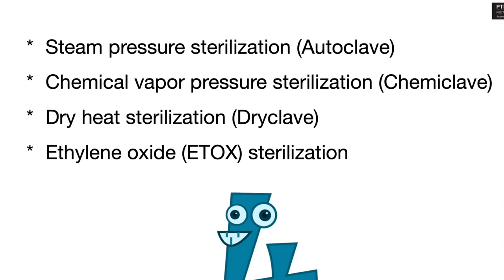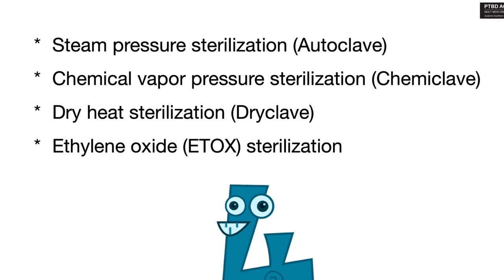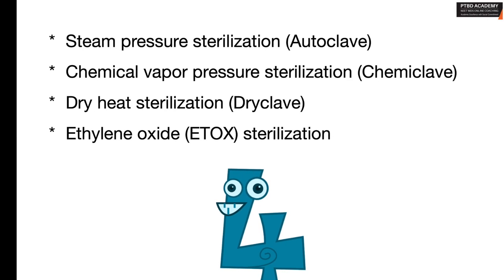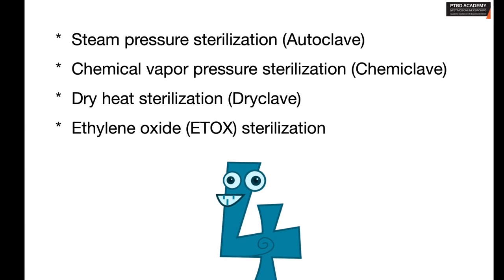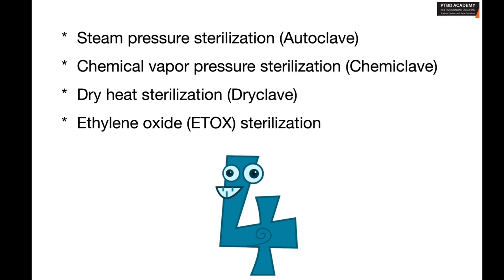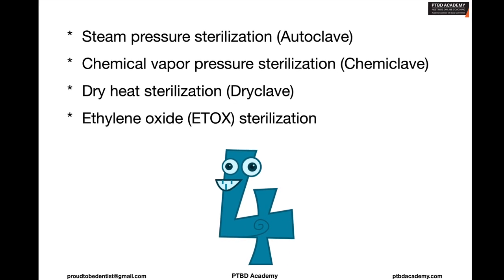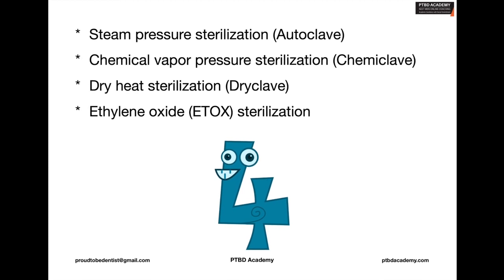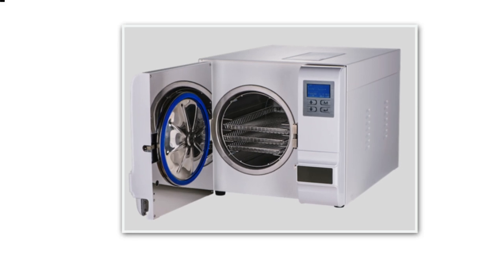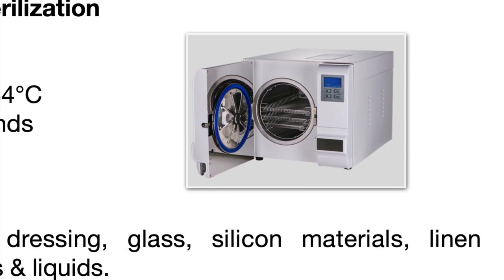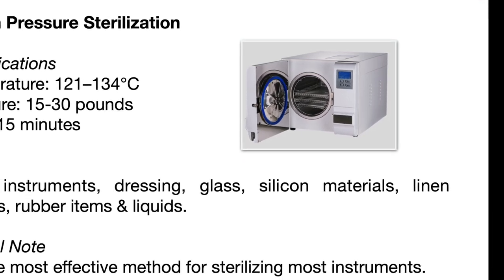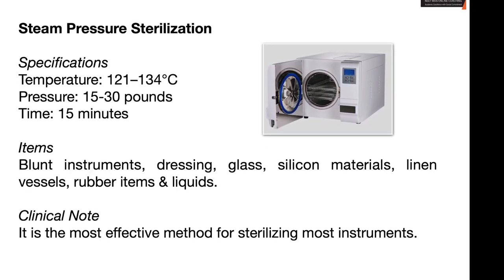There are various accepted methods of sterilization including: steam pressure sterilization or autoclave, chemical vapor pressure sterilization or chemiclave, dry heat sterilization or dryclave, and finally ethylene oxide sterilization or EtOx. Now let's look into each of these methods. First and foremost, steam pressure sterilization — this is a technique operated at a temperature range of 121 to 134 degrees centigrade.